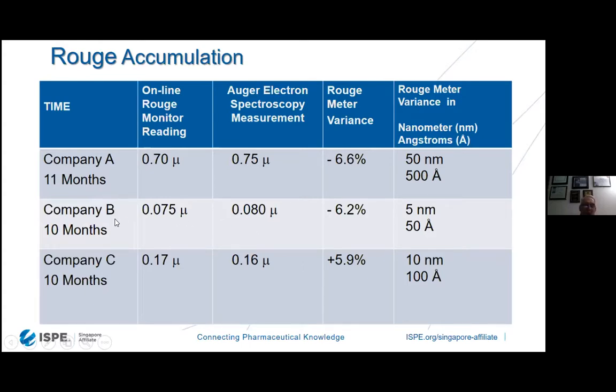This was a modern water system that was almost brand new, and it was using newer technology, 316L stainless steel, WFI water system, etc., using vapor compression distillation. Company C was a 12-year-old water system, 316L, had been derouged and passivated yearly over that time period. And you can see that the rouge rate there was a little bit higher at 170 nanometers. And the Auger showed 160. Again, good correlation between the Auger and the online.